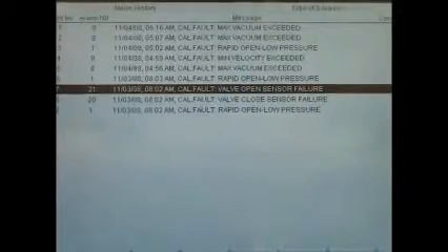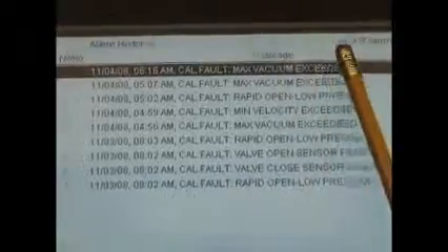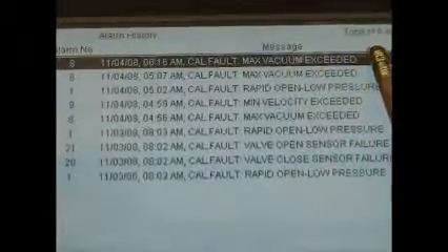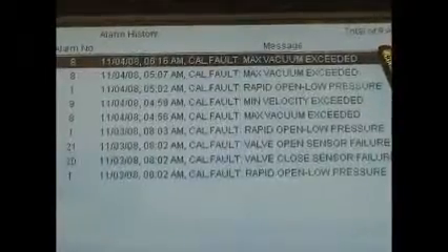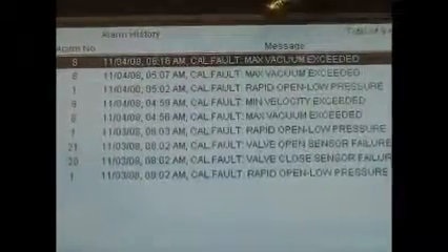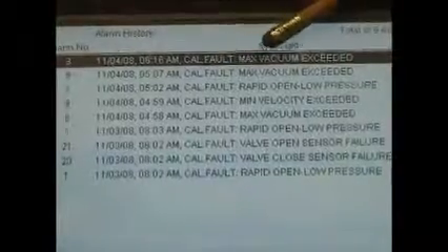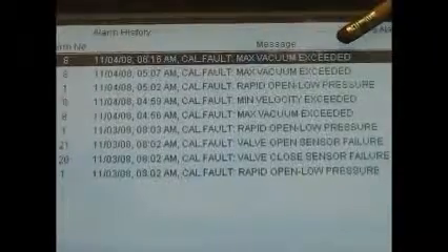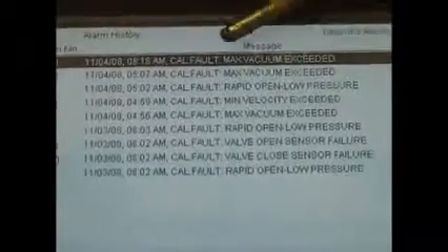So if you have a bad transducer, you can use this screen to diagnose an open or a closed pressure sensor that was causing the fault on the calibration. If, for example, on the top, we go to line up, we can see here where the reason for the fault is a maximum vacuum exceeded. For example, the unit was trying to calibrate, and the operator probably didn't catch the calibration in progress quick enough, and the vacuum spiked up into the yellow area of the vacuum gauge, which caused the calibration to fail. So here it says maximum vacuum exceeded, which would be that.